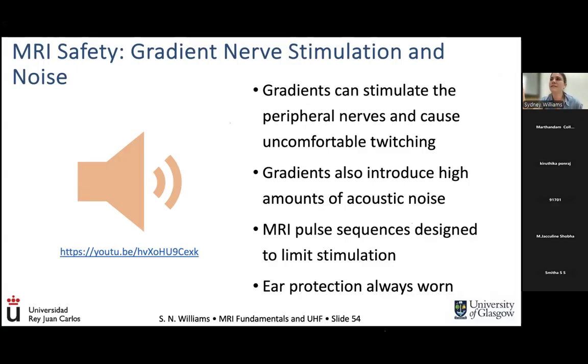And then on top of that, it's really interesting, because fast switching gradient fields while you're being scanned can actually induce small currents inside your peripheral nervous system, the nerves on the peripheral parts of your body, like your limbs. That could cause some twitching, which can be uncomfortable to someone. So a lot of MRI sequences are designed with this in mind, and they limit the amount that you can move in certain ways with these gradients during data collection, to reduce the chances of stimulating your peripheral nerves and causing discomfort. It's not dangerous, but it can be discomforting to the patient. We want to try to alleviate that.